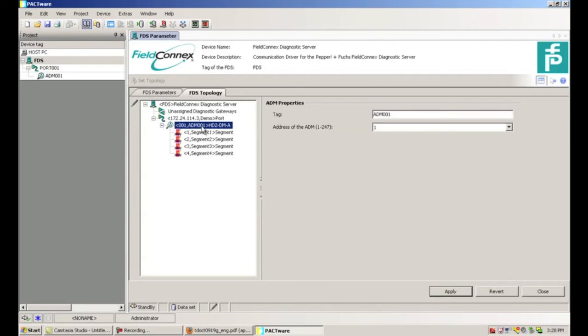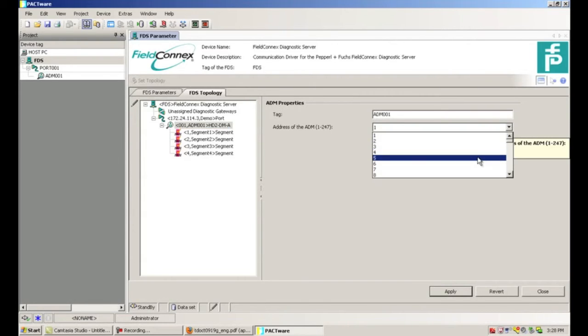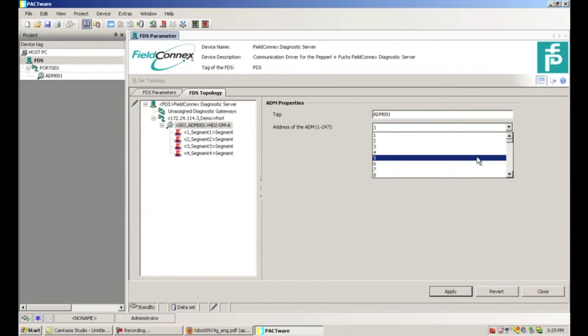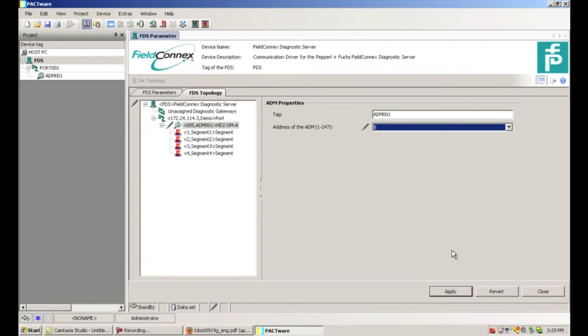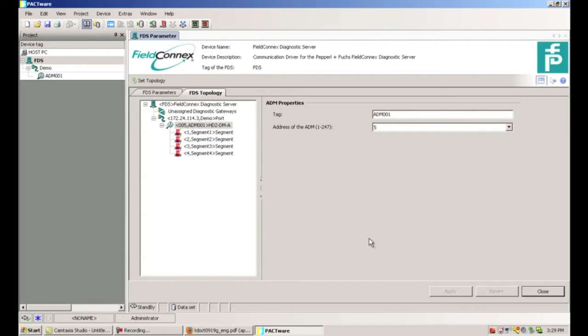The next step is to click on the Advanced Diagnostic Module — ADM001. Here we can set the RS-485 address that's set on the module through DIP switches. Ours in the demo system is at address 5, so we'll choose address 5 and click Apply. Once you click Apply, that sets the topology. You can see that the device tag for the port name changed from generic port to Demo — the name we assigned to the Ethernet converter — and we're ready to go.